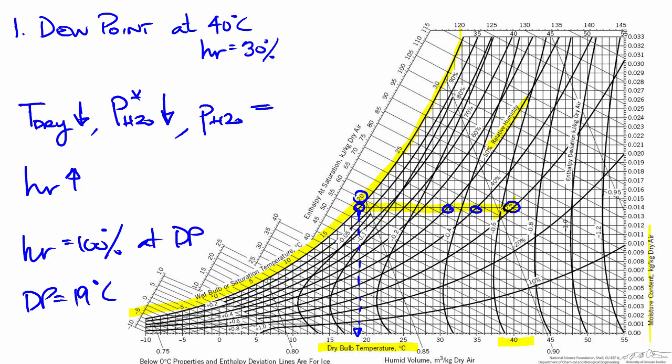The dew point represents the point at which liquid will first start to form. If we continue to lower the temperature, we would move along the saturation curve, continuing to condense water. As we move down along the saturation curve, we are also lowering the moisture content as that water condenses.